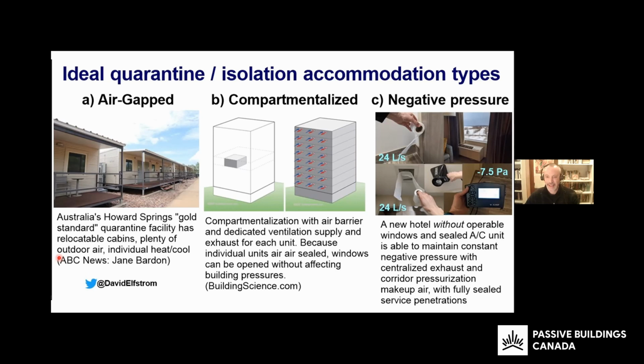It turns out with mixing, it's just like adding cream to coffee, or trying to dilute. You're having to dilute the air. Every amount you put in, you have to remove some, and it's always a mix. So with one air change in a fully mixed room, you reduce the concentration of a contaminant by 63%. So 37% still remains. You do another air change, another 37% remains of that. Do another air change, and at that point 37% three times, you're at the characteristic 3 air changes equals 95% reduction.